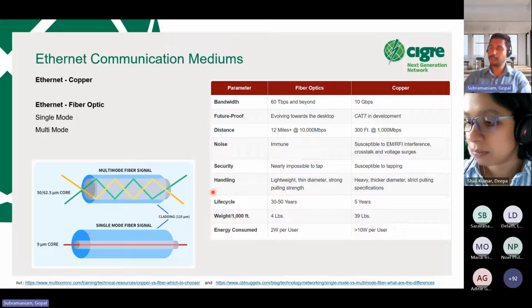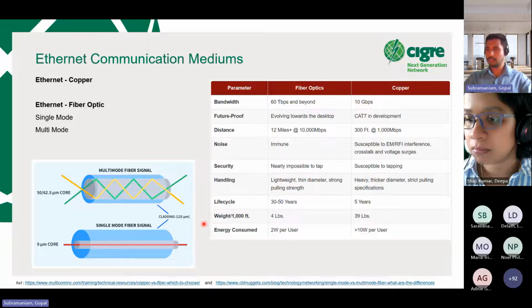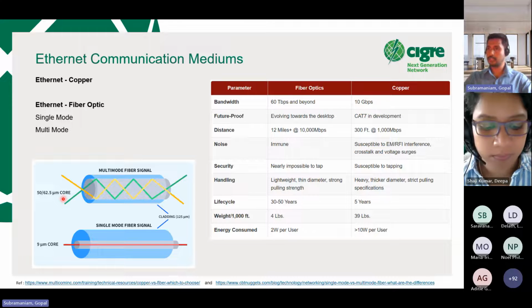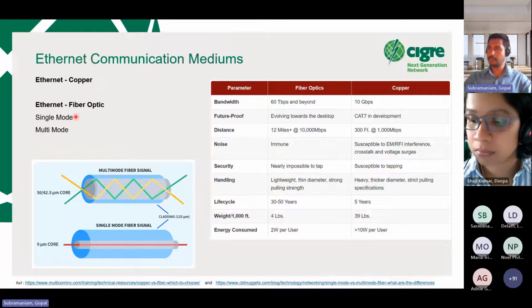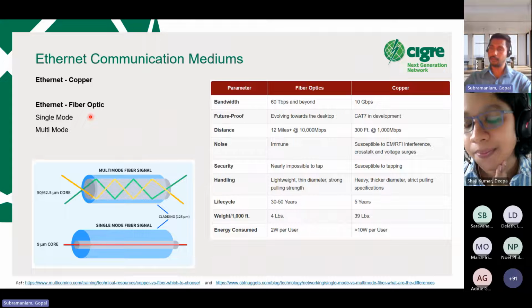And these are the communication media, like Ethernet. It can either be copper or fiber optic. In fiber optic, we have single mode and multi-mode cable. Single mode cable will have a single signal sent, and there will be less distortion, so it can be used for long distance communication. Multi-mode cable can carry multiple modes of signals, and this is generally preferred for communication within the substation, for substation automation applications. And single mode is generally preferred for line protection applications, for example, line differential protection.